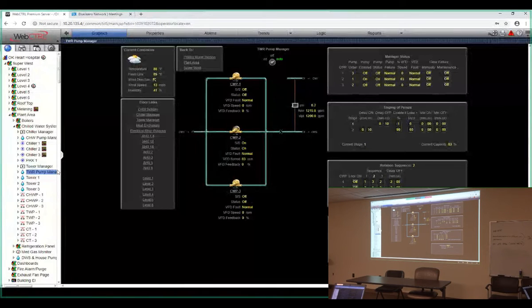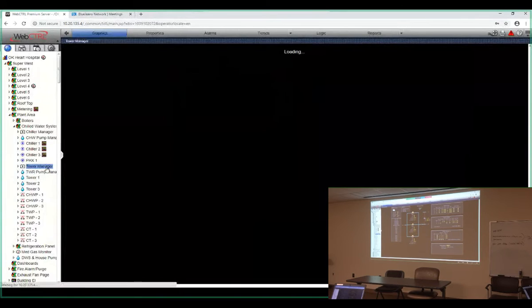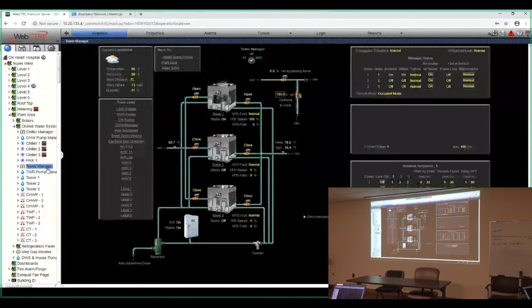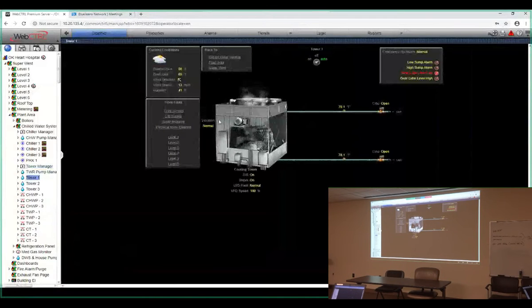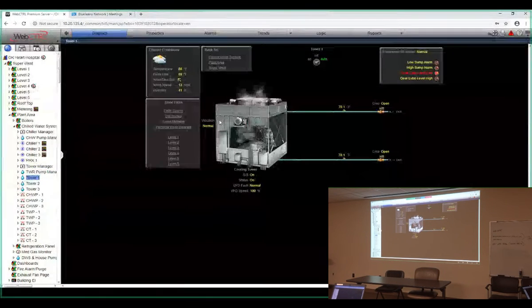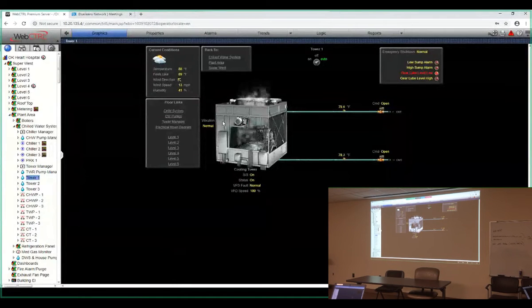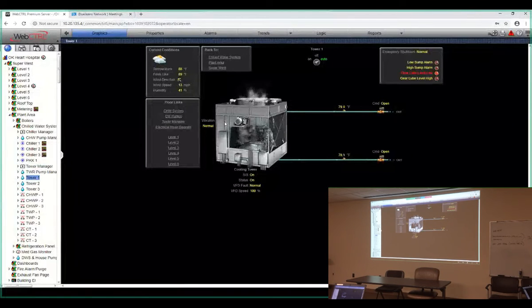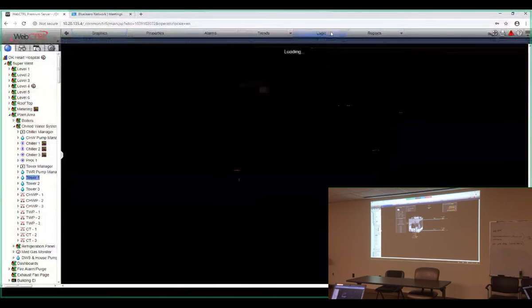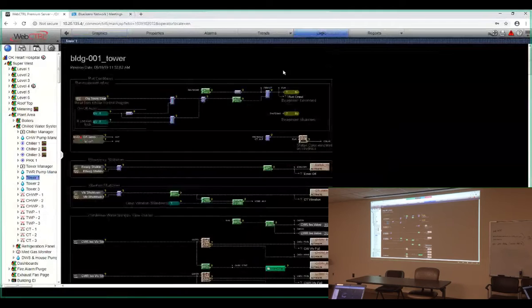What's controlling the fans? Did you already cover that? Nope, we can go over the fans. So click on tower 1. I do want to mention, as you see, we're running tower 1 with chiller 1 and tower pump 2. It doesn't matter which pump, which tower. The systems are essentially isolated from one another, so that portion of it doesn't matter. I have to go to the logic because I don't remember what runs the thing. Scroll down for me.